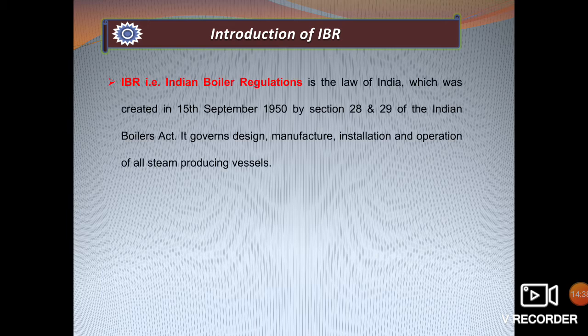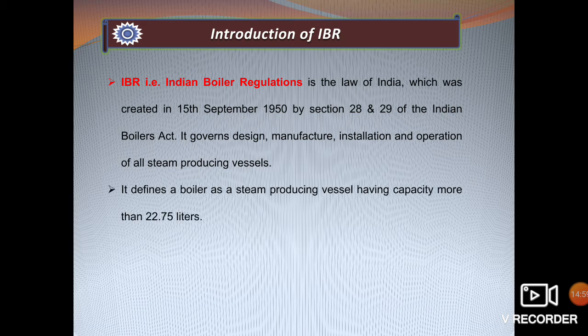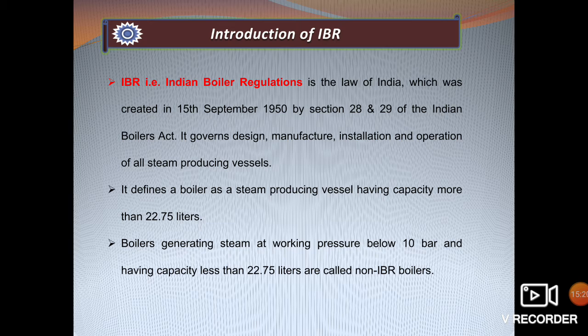IBR — Indian Boiler Regulation — is the law of India created on 15 September 1950 under sections 28 and 29 of the Indian Boilers Act. It governs the design, manufacture, installation, and operation of all steam-producing vessels. It defines a boiler as a steam-producing vessel having a capacity of more than 22.75 litres. Boilers having more than this capacity come under the Indian Boiler Regulations Act. Boilers generating steam at working pressure below 10 bar and having a capacity less than 22.75 litres are called non-IBR boilers.